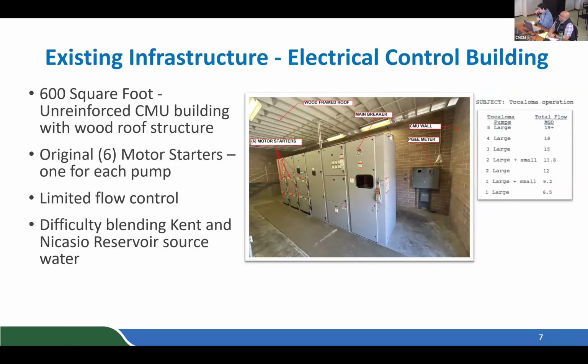Okay, now we're inside the electrical building. It's comprised of unreinforced concrete masonry unit walls, which are not seismically resilient. It also has a wood framed roof structure. This houses the original 6 motor starters, and there's one for each pump. I like to think of these as standard light switches. So when you turn the switch on for one of the pumps, it turns on immediately and it goes to full speed. And there's no changing that full speed. So it's running at 1800 RPM, and there's no ability to control it.